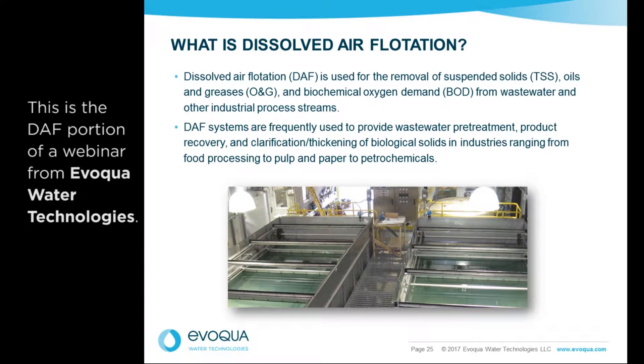Dissolved air flotation, or DAF, is the exact opposite of gravity settling — we're trying to get things to float. As a treatment technology, DAF has been around a long time, at least 50 years. It's not as old as gravity clarification but is fairly mature. It is most commonly recognized as a pre-treatment for the removal of suspended solids and oils and greases from industrial wastewater, but is also used for secondary clarification, thickening of biological solids, and as a tertiary treatment for the removal of algae and phosphorus in many final discharges.